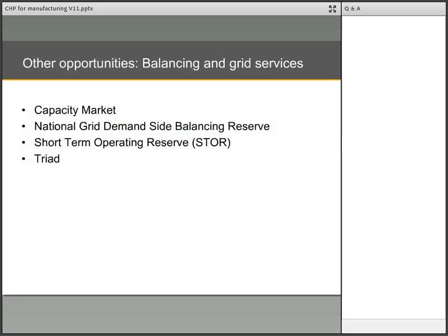There are opportunities for CHP generators to benefit from generating power on site, especially as we approach a period over the next few years where electricity market capacity is falling and there's increasing pressure to find necessary electricity for the grid. CHP generators can take advantage of this by providing balancing and grid services, capacity services such as the capacity market, the demand-side balancing reserve, the short-term operating reserve, and through Triad.